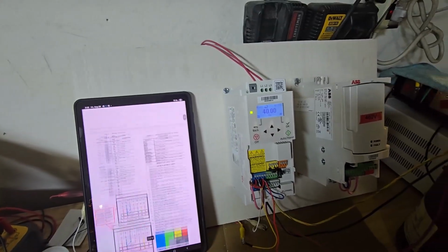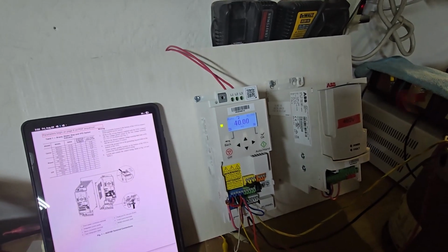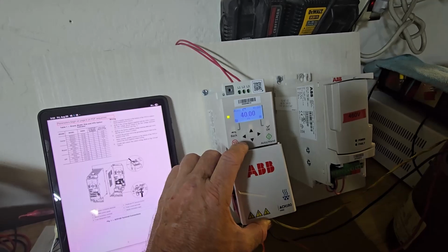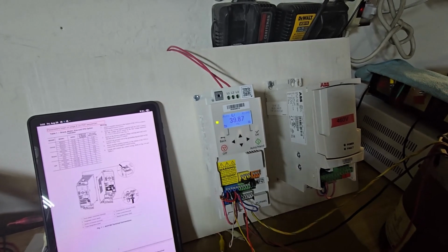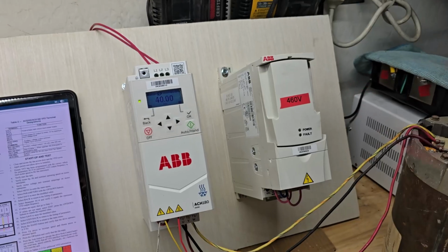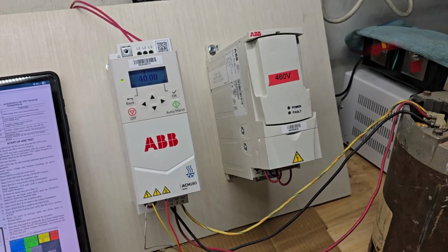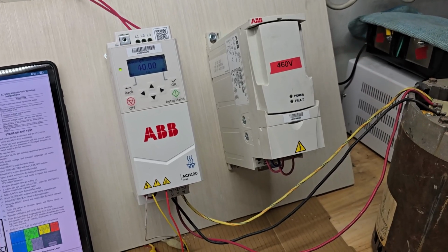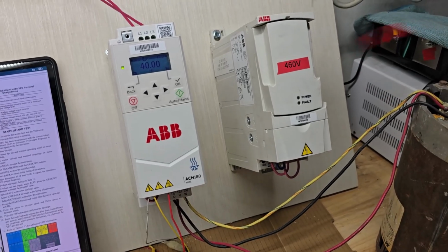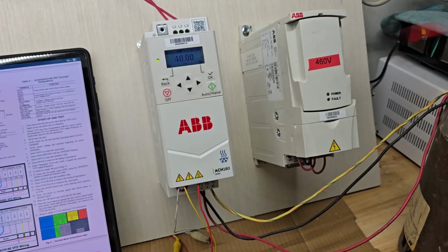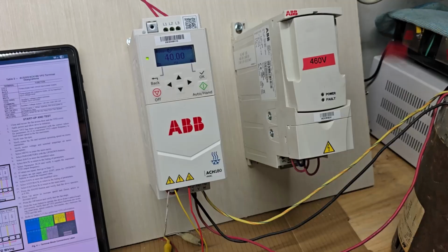And that's it, and that's how you program the ACH-180 drive, specifically here for Carrier staged air volume units. That will be small, medium rooftop units and the commercial split units. With the newer equipment, including the commercial splits, they're now using that axial fan, known as EcoBlue. It just uses a varying 2 to 10 volt signal input and a board or direct signal from controllers. So you no longer have to deal with the drives on the new units, you'll just have to deal with the drives for replacement on existing units.